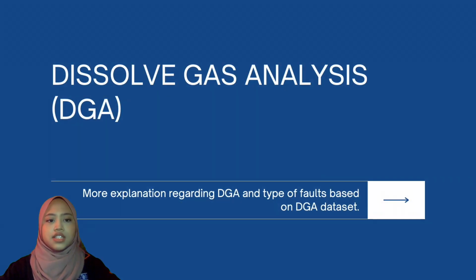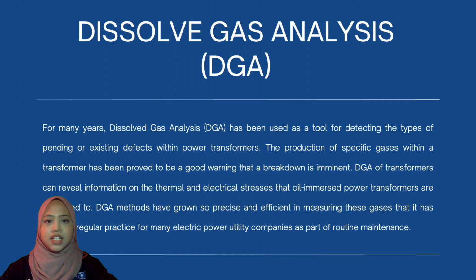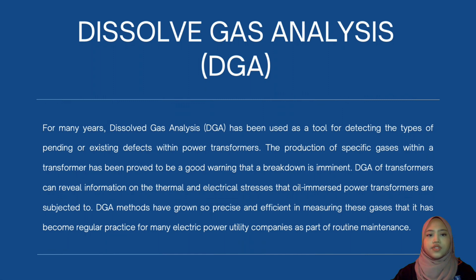Next is dissolved gas analysis. For many years, dissolved gas analysis, DGA, has been used as a tool for detecting the types of pending or existing defects within power transformers. The production of specific gases within a transformer has been proved to be a good warning that a breakdown is imminent. DGA of transformers can reveal information on the thermal and electrical stresses that oil-immersed power transformers are subjected to. DGA methods have grown so precise and efficient in measuring these gases that it has become regular practice for many electric power utility companies as part of routine maintenance.